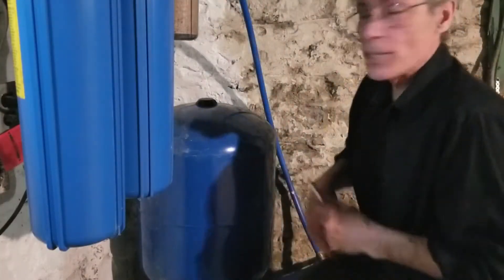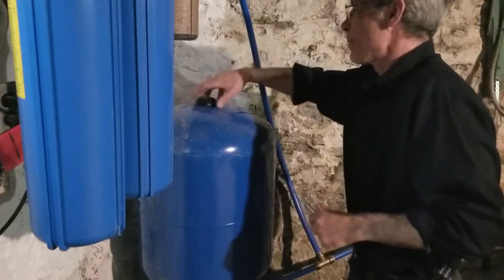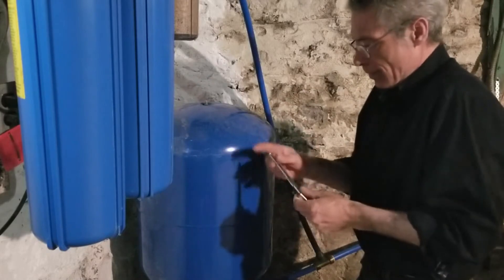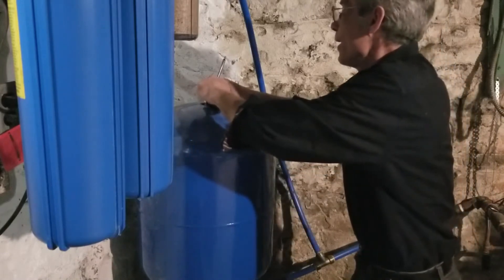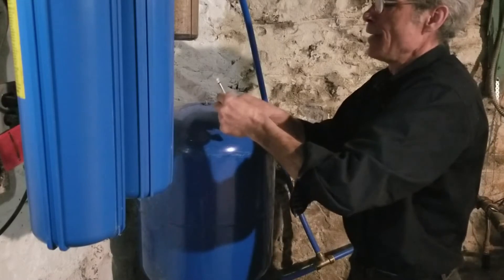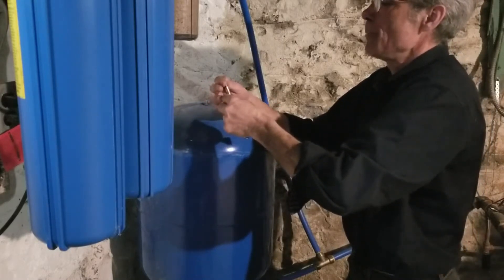We brought our water pressure down to zero and we're going to take off this top cap here. We have a needle valve, and this valve is the same as what's in your car to fill up a tire basically. We're going to put a gauge on that and see what the pressure is — it's reading at just over 10 psi.